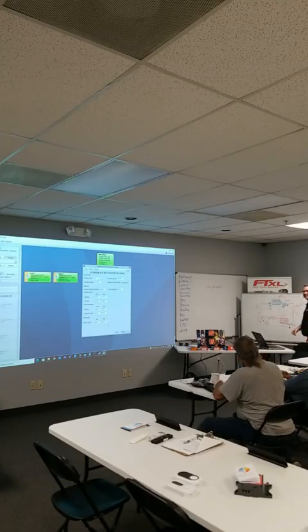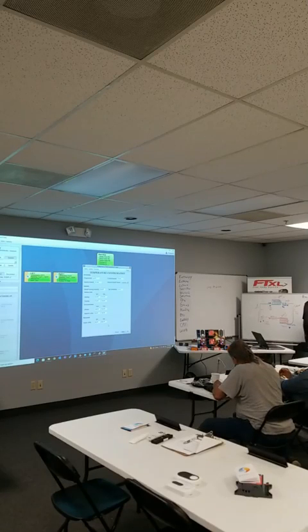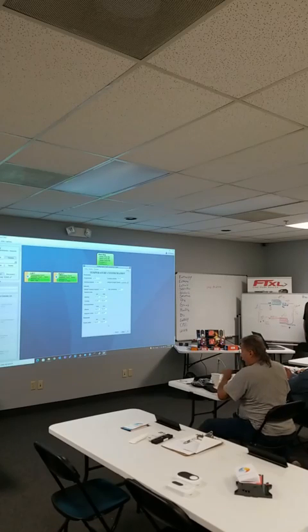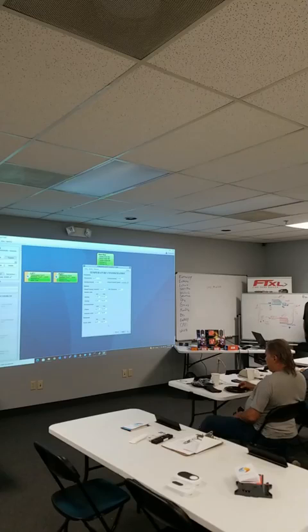One of the cool ones we just had: Tom and his team put a VAV system in for a longtime client who'd had a lot of problems with temperature and humidity, and we went with PROLON. It wasn't until later in the project that we found out about the humidity issue. All we had to do was add a couple humidity sensors to the PROLON system, since it has dehumidification built in, and it's been dehumidifying the building. I talked to Mike today and nobody's complained about humidity the past two days. If there was gonna be a humidity problem, it would have shown by now.